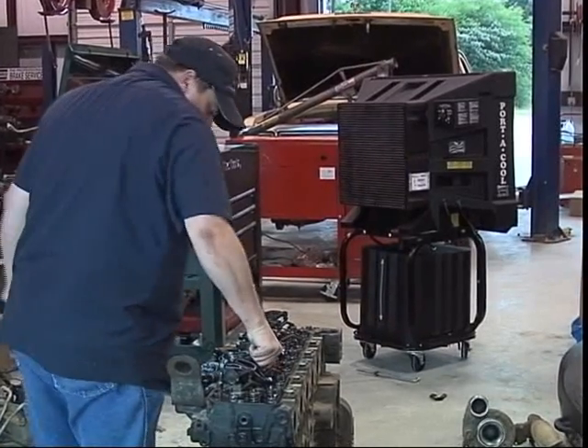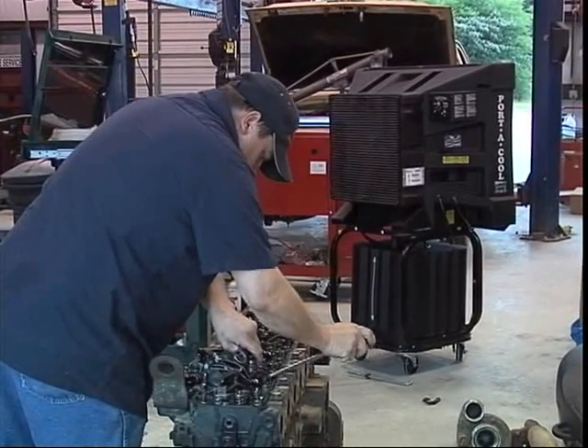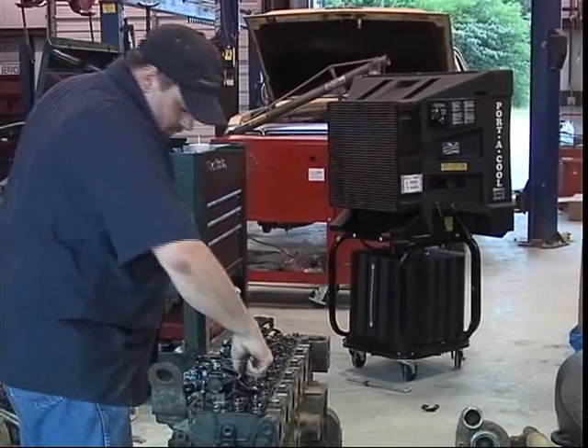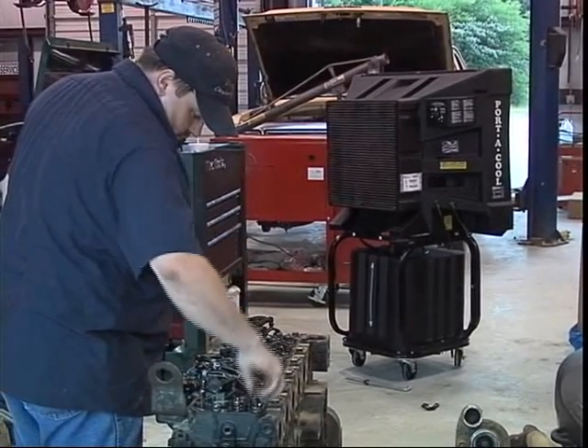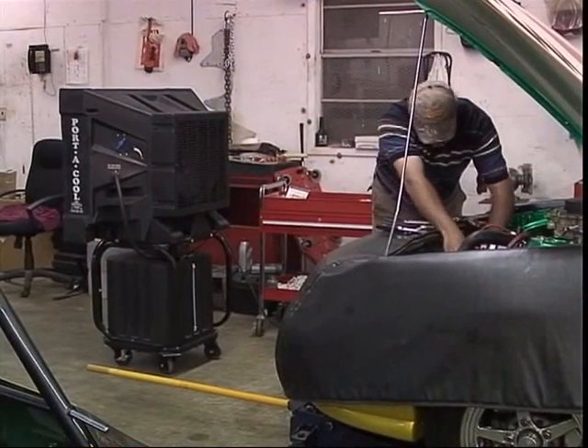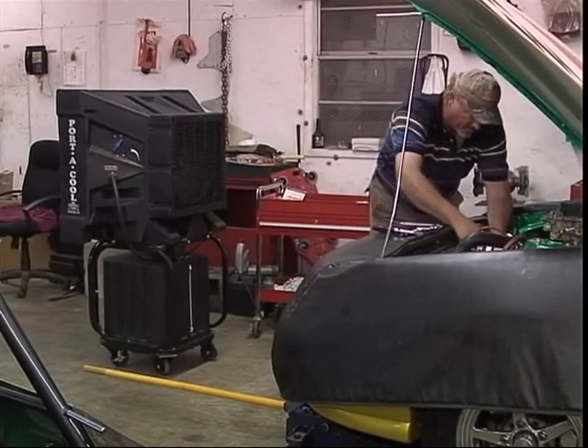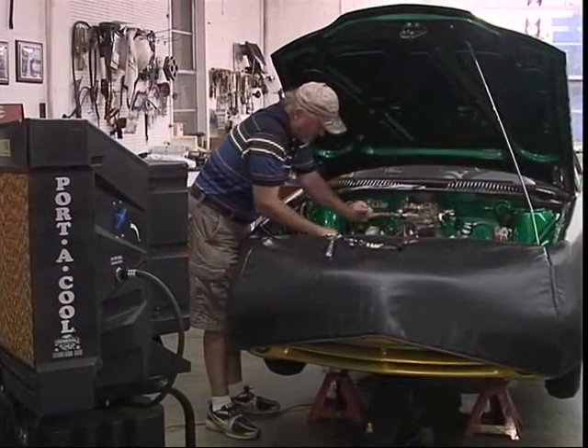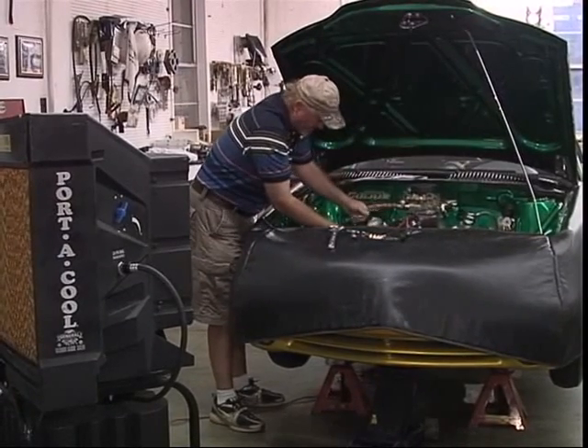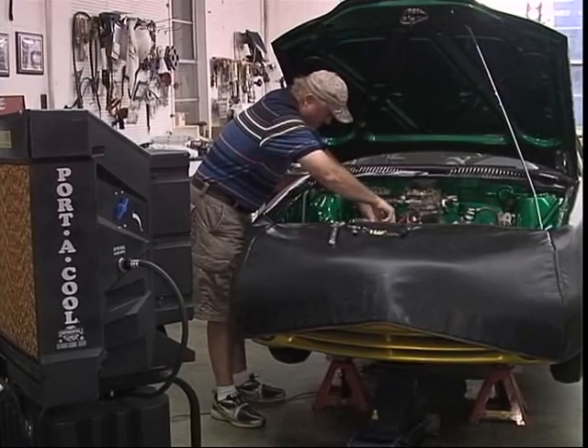If your relative humidity in your area is lower, your Portacool unit can evaporate more water and facilitate a more dramatic temperature drop. You may adjust the valve accordingly to achieve maximum cooling for the climate in your area. Portacool units cool effectively even when the humidity is high. Water flow can be adjusted down to prevent excess humidity. In high humidity conditions, the 6-inch cool pads allow water to contact with surrounding air for the highest level of evaporation possible.